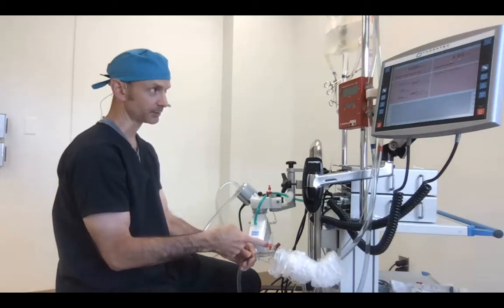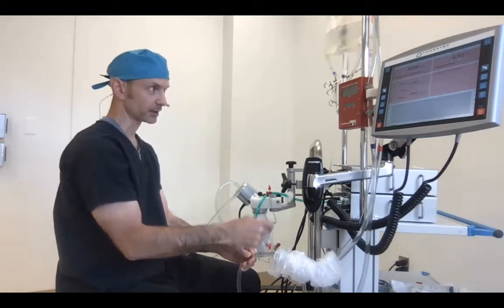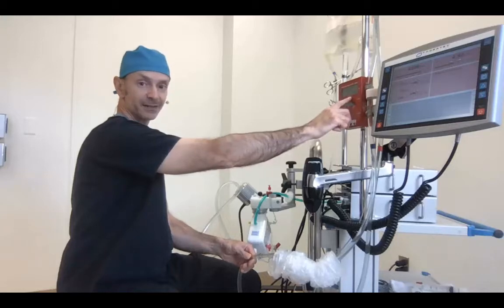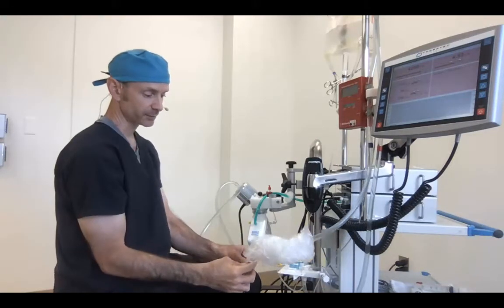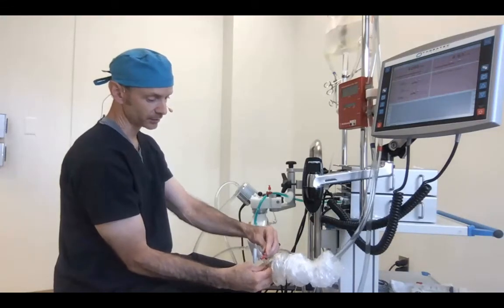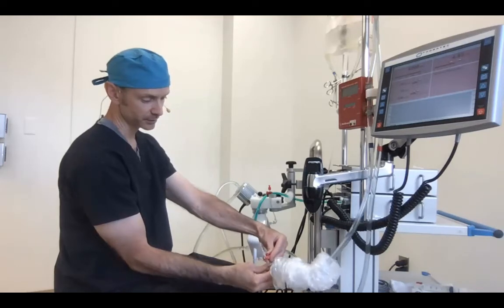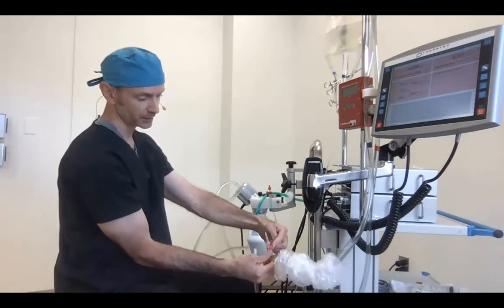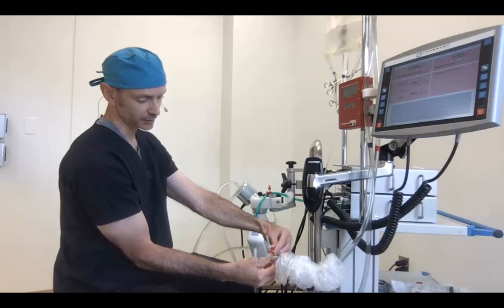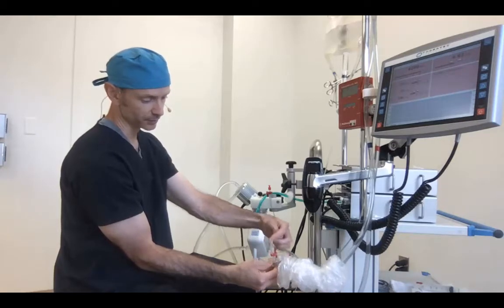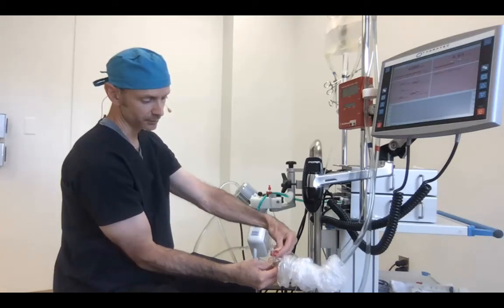If I open this stopcock, it'll suck in air because, as you can see, we're reading minus 53 right now. Let's confirm that the 0 is accurate here. I'm going to turn this off to my circuit and take this stopcock here. That's part of the DLP set. And I'm going to turn it so that it's off to the circuit but open to my pressure transducer, like that.